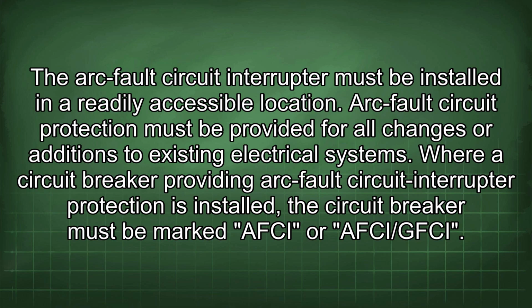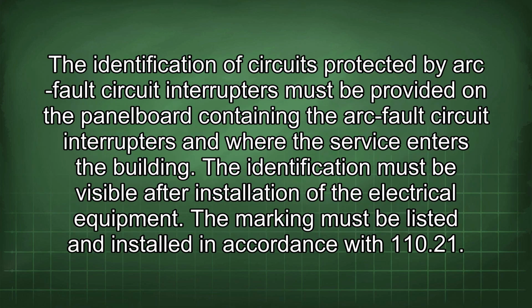Where a circuit breaker providing arc fault circuit interrupter protection is installed, the circuit breaker must be marked AFCI or AFCI/GFCI. The identification of circuits protected by arc fault circuit interrupters must be provided in the panel board containing the arc fault circuit interrupters and where the service enters the building. The identification must be visible after installation of the electrical equipment. The marking must be listed and installed in accordance with 110.21.